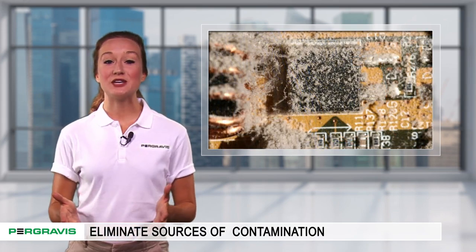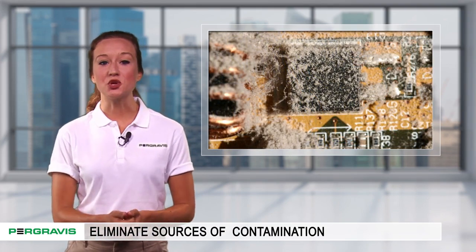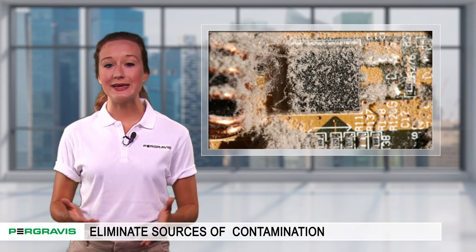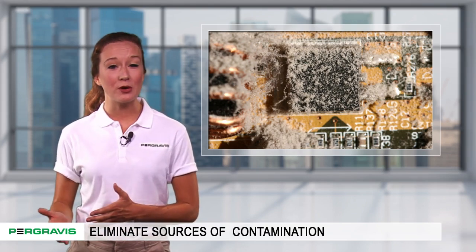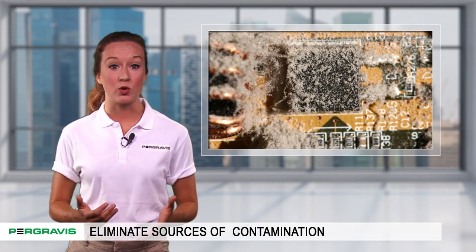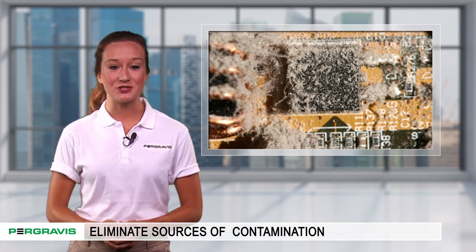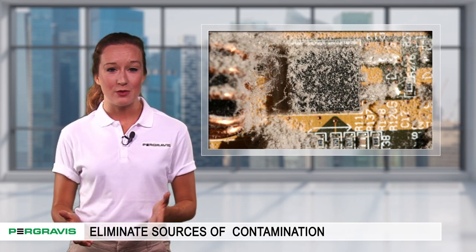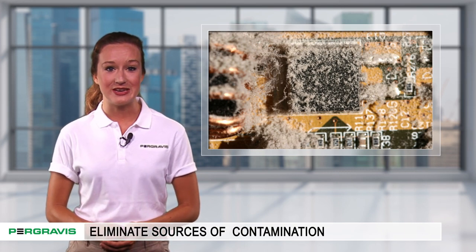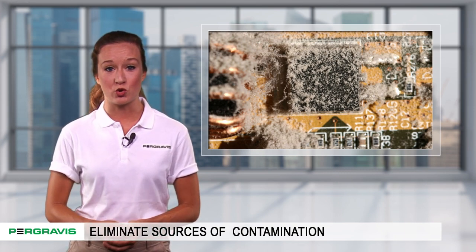Data center contamination is a big issue. It is essential that rooms housing servers remain clean and free of debris, since small particles can get sucked into vents and exhaust ports and cause critical failures. Some common materials found in data centers can be a source of contamination, which in turn impacts cooling efficiency and poses a potential risk of circuit board shorts.